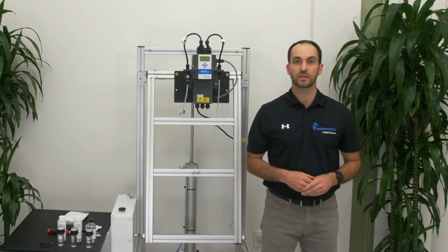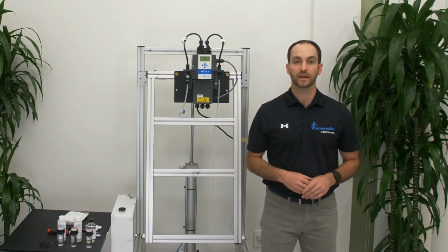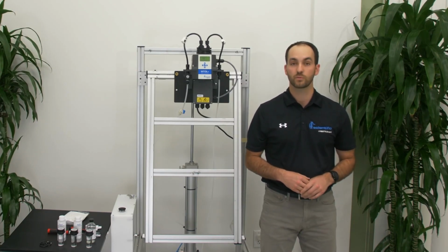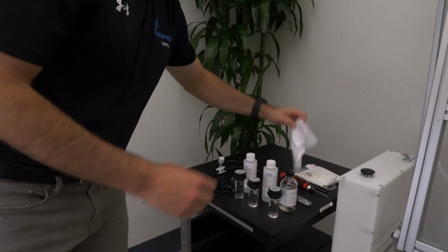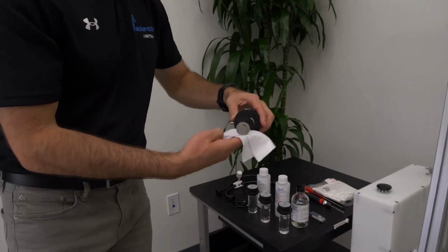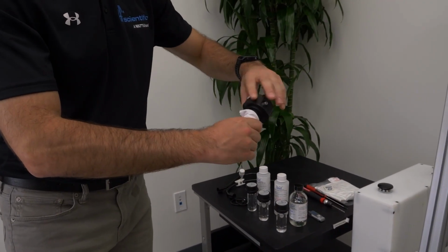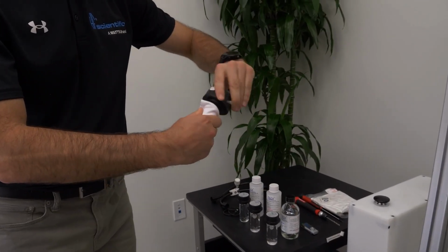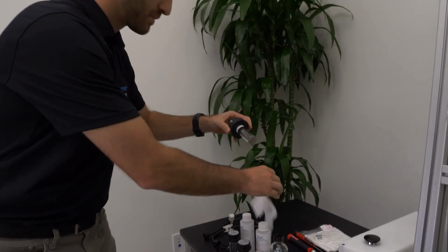Remove the desiccant from the cuvette and screw the cuvette back onto the flow head, using care not to touch the sides of the cuvette where the measurement occurs. Wipe the cuvette with the soft cloth provided in the calibration kit and use the locking cam to secure the flow head by rotating the cam around the pins.